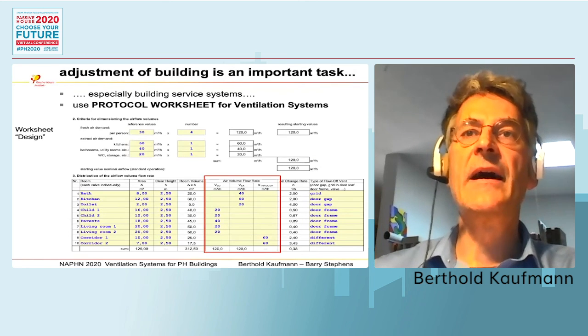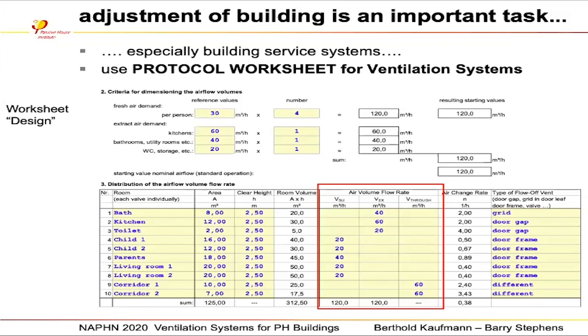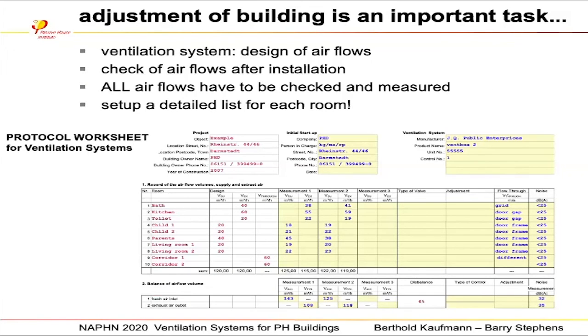Well, the last point is the adjustment of the system. Here you have the numbers out of the design for each room, in cubic meters. On the next slide is a table which could be provided to the operation people who did the installation and who do the measurement afterward. They see the numbers from the design, and in the empty part they enter their measurements. The idea is that the disbalance should never, in reality, be more than 10%. And so it's good enough.